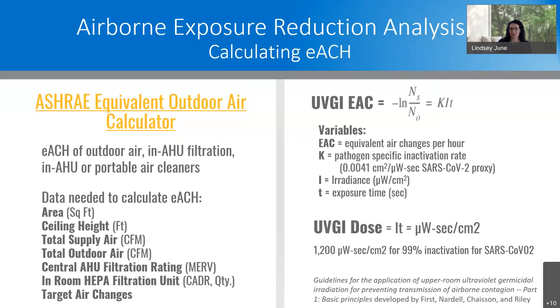A quick side note on UVGI dosing. The UVGI dose is the irradiance times the exposure time. Our study found inconsistent guidance of dosing levels needed to achieve 99% inactivation on a single pass for coronavirus, but about 1200 microwatt seconds per centimeter squared seems to be the most supported value. UVGI manufacturers have detailed calculators to determine the appropriate dosing levels needed for a specific UVGI configuration, but be cognizant of the target dosing levels they're using to avoid oversizing systems and excessive energy use.